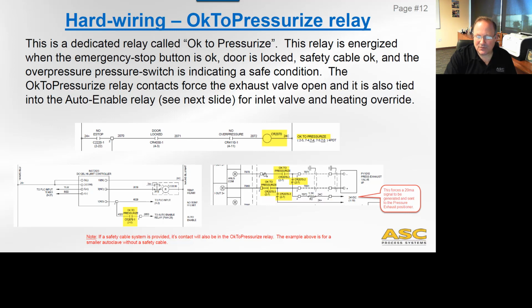And right here you see that if we're okay to pressurize, we have normal control of our exhaust. But if we're not okay to pressurize, not being normally closed, we actually feed a forced 20 milliamp into that exhaust valve to make it wide open. And that's done by running 24 volts across a known resistor, which provides a specific milliamp, 20 milliamps, to that unit. Now this specific image is not including the safety cable, because this was taken from a smaller autoclave that didn't have a safety cable system. But with the larger systems, the safety cable would also be here.